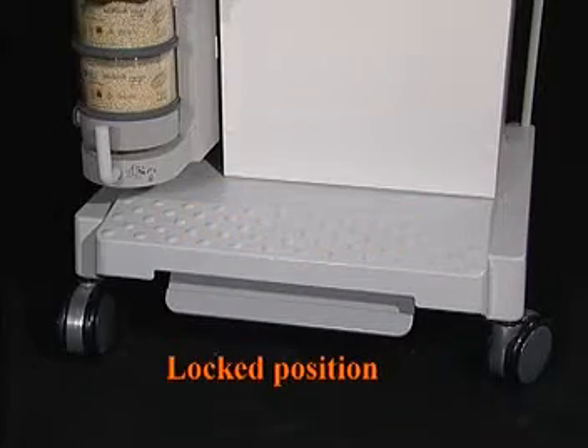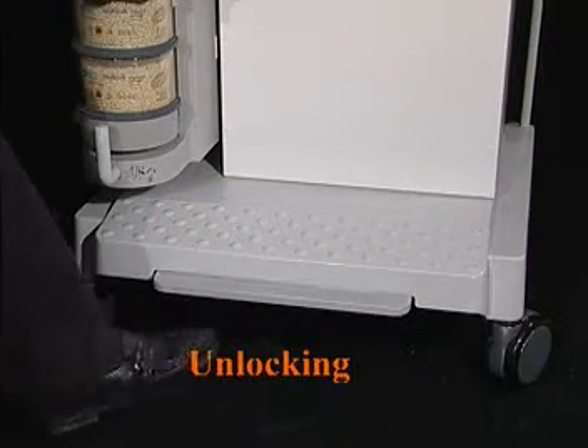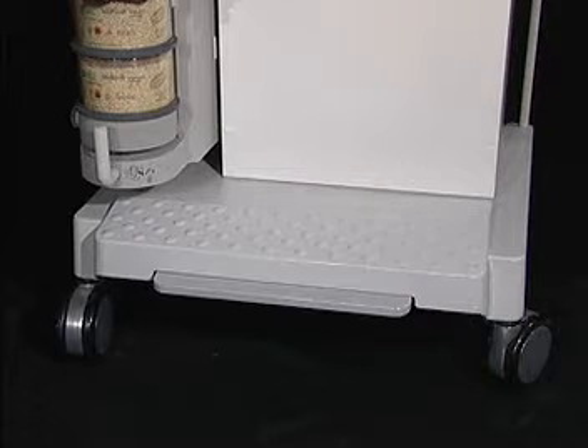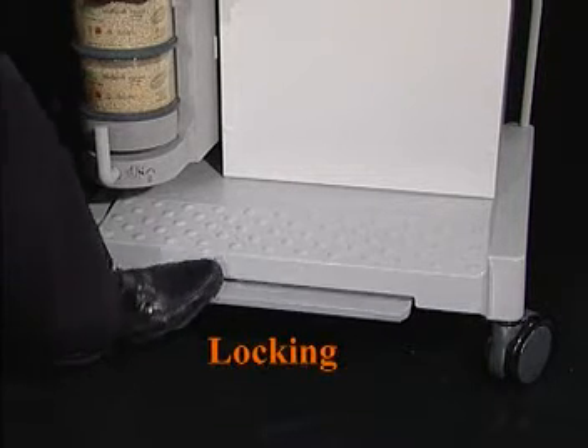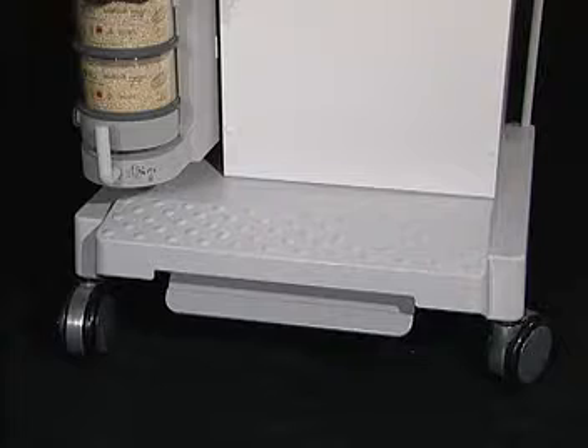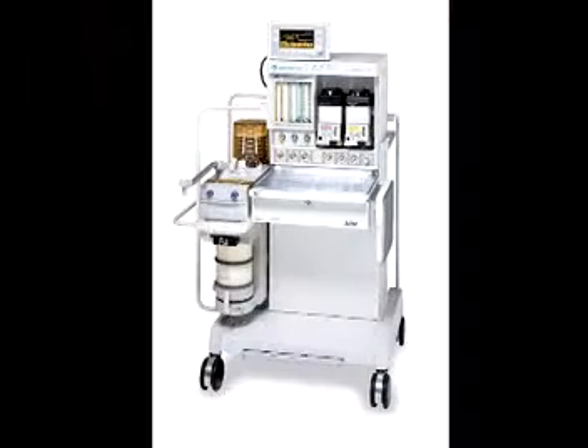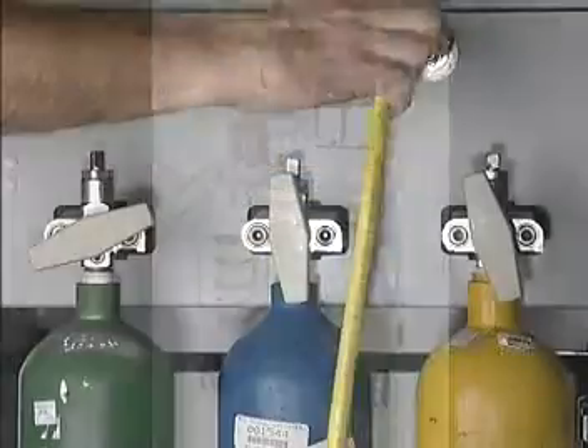The Aestiva features a central foot brake which can be activated without regard to the position of the casters. It is important to relock the brake if the machine is repositioned during a case. Locking of the casters is especially important in the MRI environment, as the unit does contain a minimal amount of ferrous material. The MRI unit must be placed outside the 300 Gauss line.